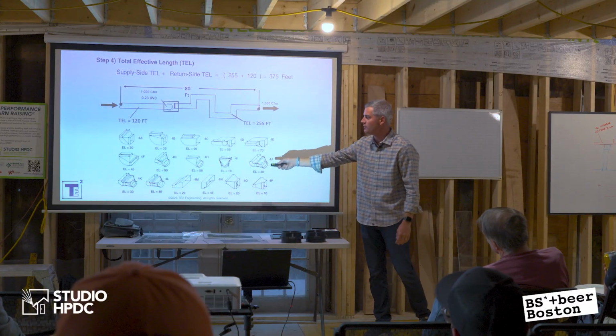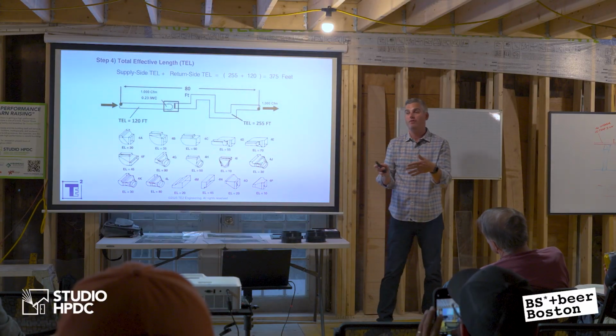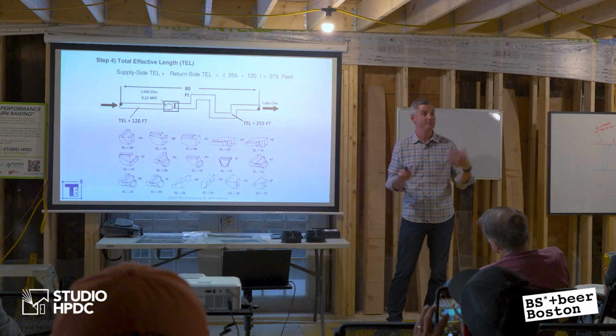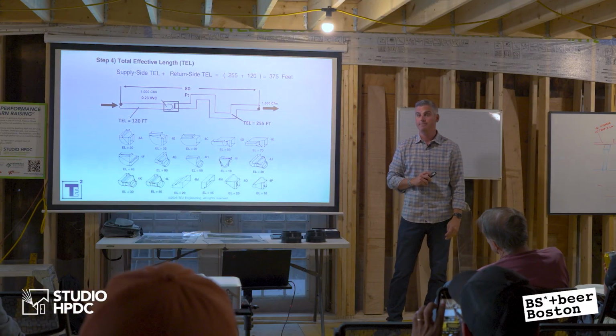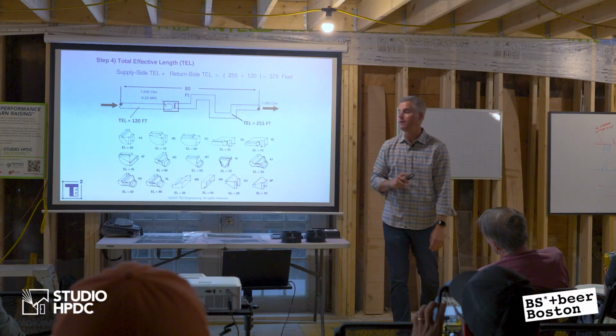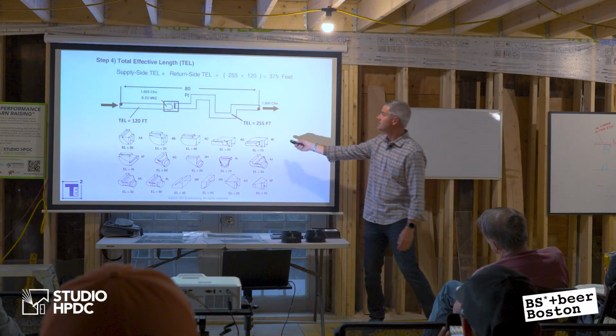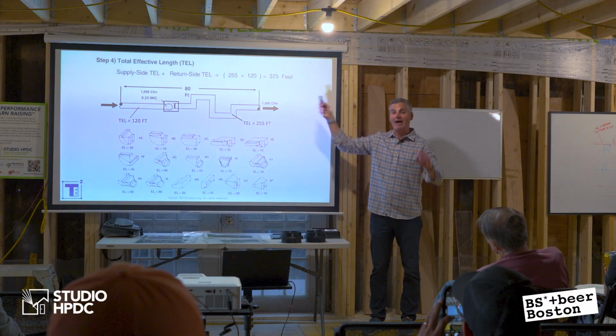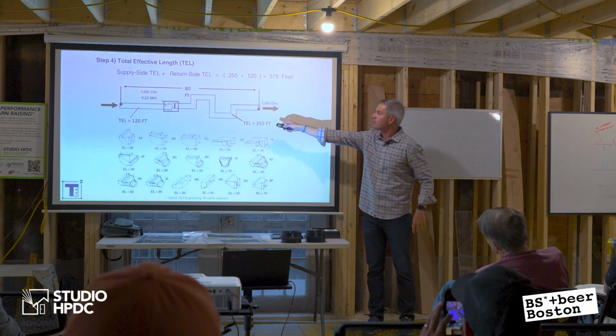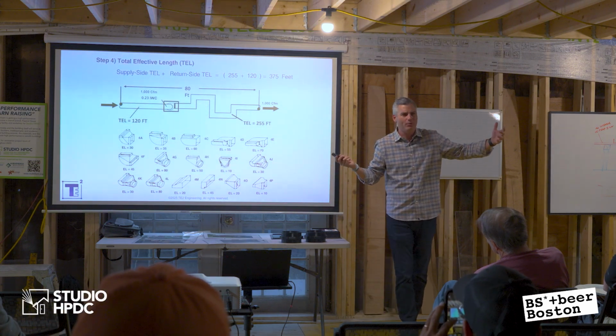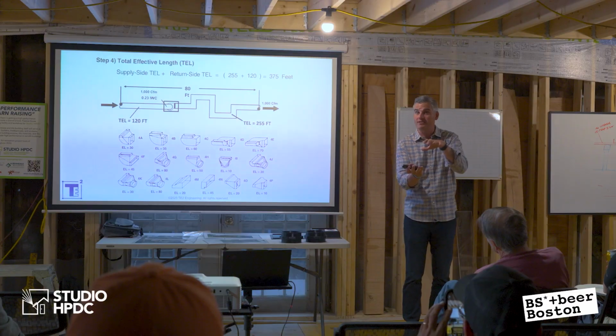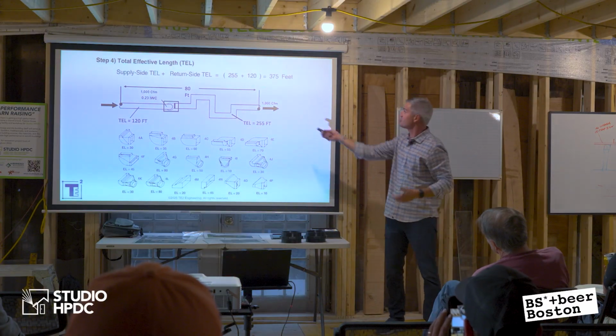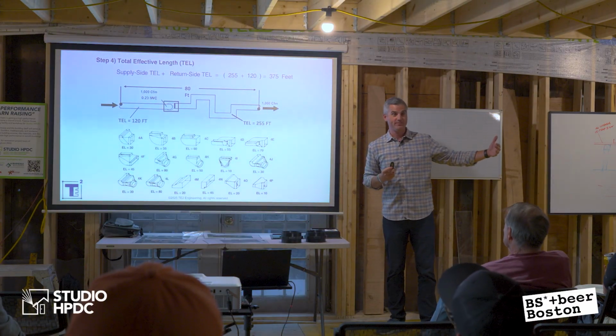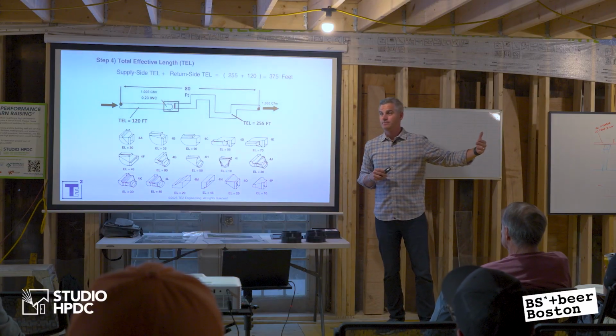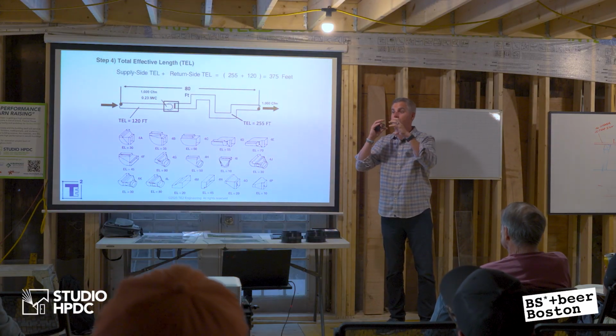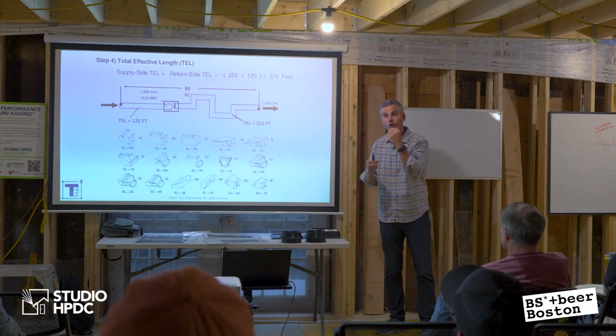This one, 45. So if you think that the fittings matter, if I had a lot of crappy fittings, yeah, it does matter, right? Friction measurement? Friction measurement, exactly right. So the total equivalent length of this job might be 375 feet, even though the duct run is only 80 feet. Everyone's like, it's 80 feet, no big deal. Yeah, 80 feet with the wrong size duct with a bunch of bends, that represents 375 feet on my blower motor. That's a problem, right? It's like trying to blow through one straw instead of 10 straws. A lot harder to go through that, right?